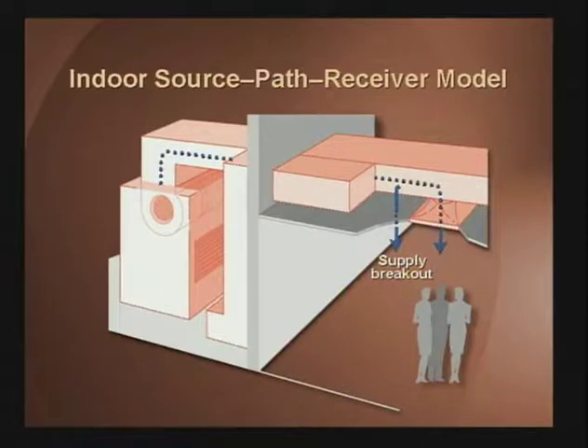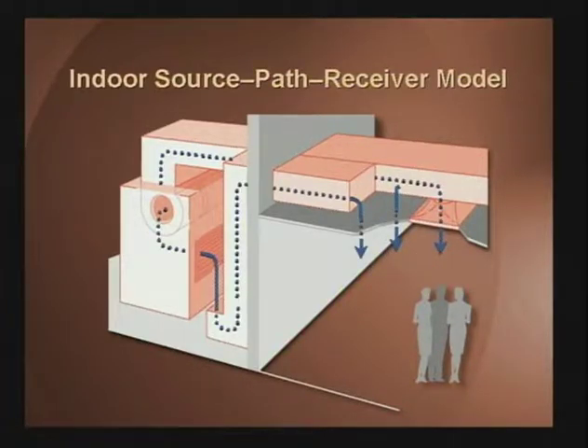But sound can also travel opposite the direction of airflow. In this case, there's a short piece of return duct, but it's not connected to the unit. The sound that's radiated into the equipment room, a portion of that sound goes into that return duct, up into the plenum space, and down through the ceiling tile into the space. That's the return airborne path. And then the last path here is the sound that travels directly through the wall between the two rooms, and that's the wall transmission path.